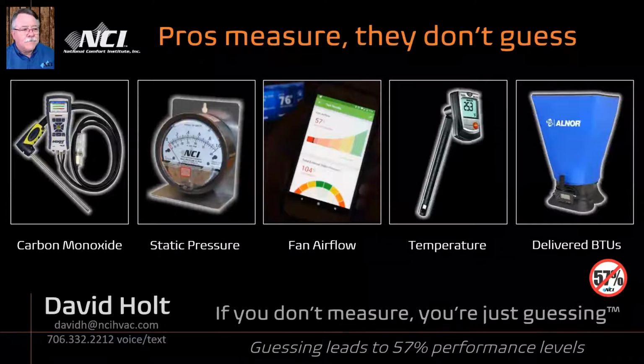Static pressure is a great way for us to figure out fan airflow. There's a lot we can do with it, but the most important thing is: do I get the proper amount of air out of that fan, yes or no? If I'm not, I need to make adjustments to the rest of the system to get the proper amount of air out of that fan.